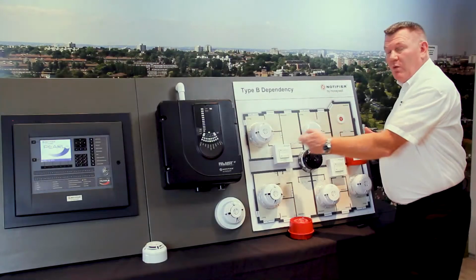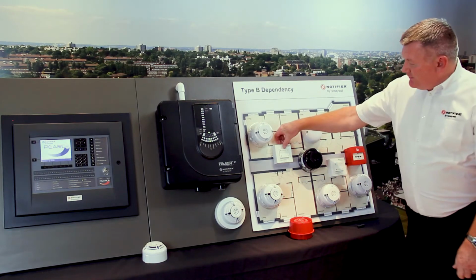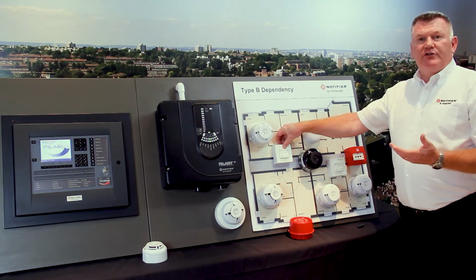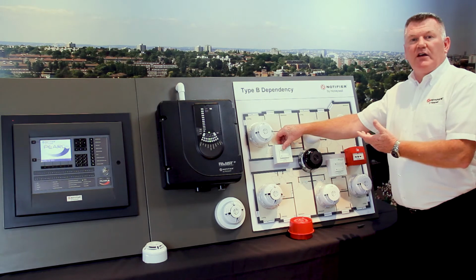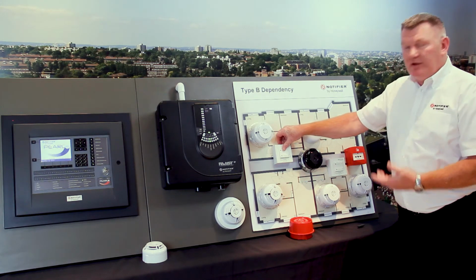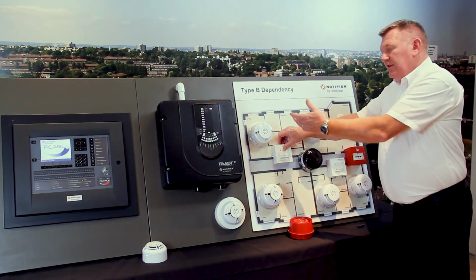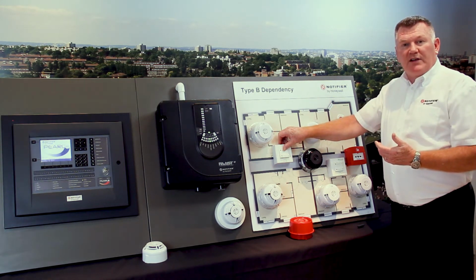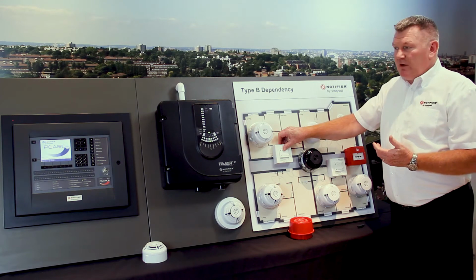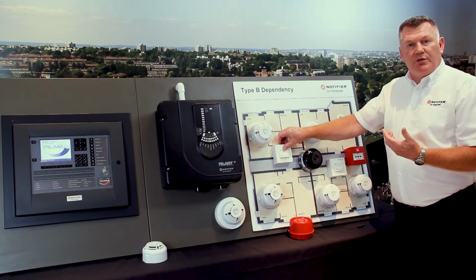So if we come back to this local silence button within flat 1, what I'm going to do here is do a fire alarm test. This would constitute a weekly test of the sounder within the flat. If I press the button and hold the button down, it'll operate the sounder and the flashing beacon for the period whilst I hold the button down. Once I release the button, the sounder will stop.